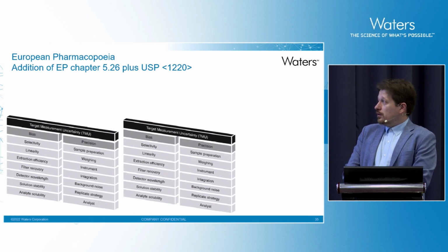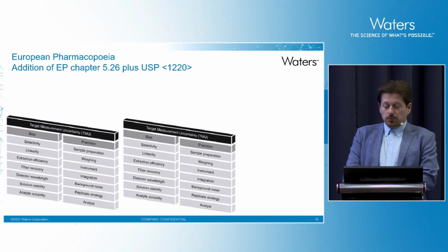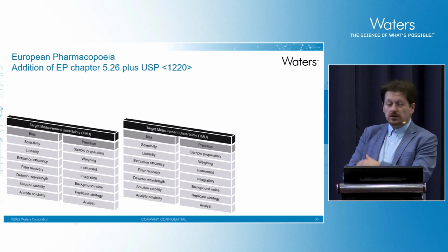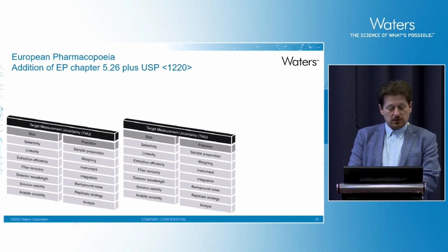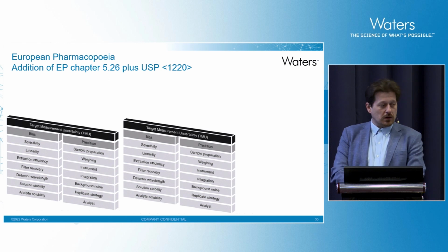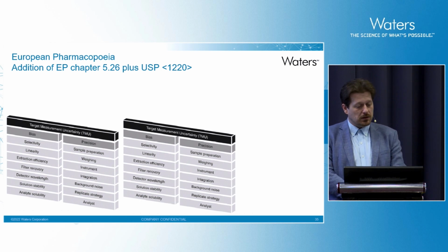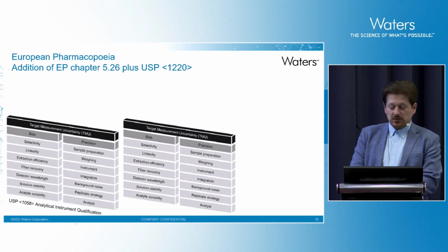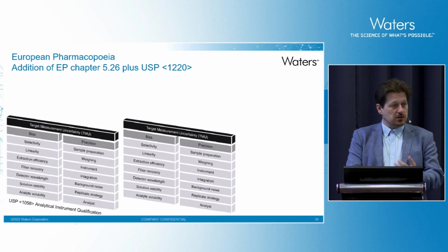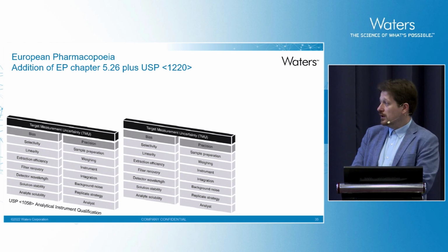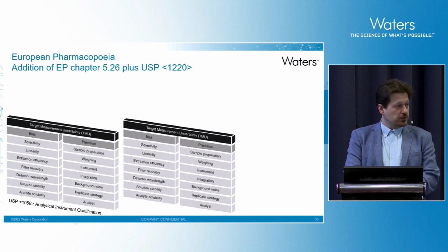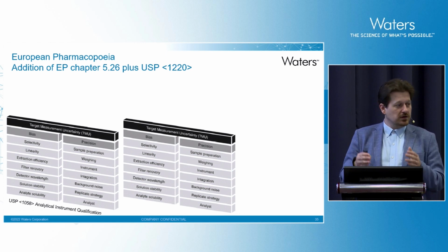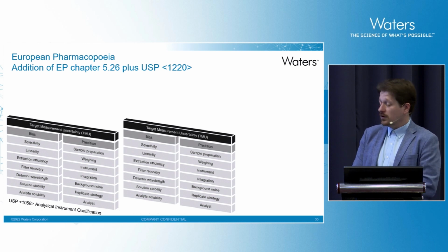When we look now very close to the chromatographic method, we may see a lot of things that can change the result. Yeah, it can be equipment with background noise, how precise is the pumping, is the detector okay. These are things we can capture by qualification, annual qualification of the instrument. There's also the chapter 1058 in the book. Please do it. They say the fundament of the good method, even before system suitability, is a qualified equipment that you can trust produces the right outcome.